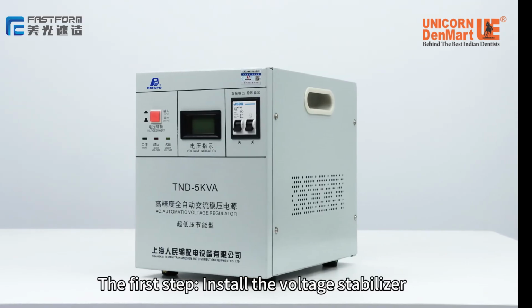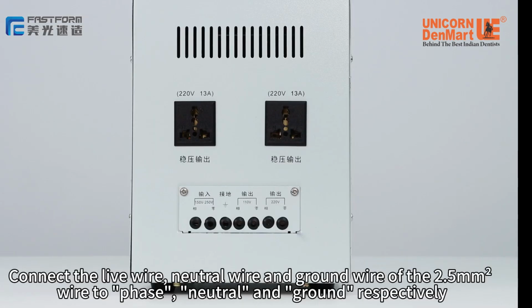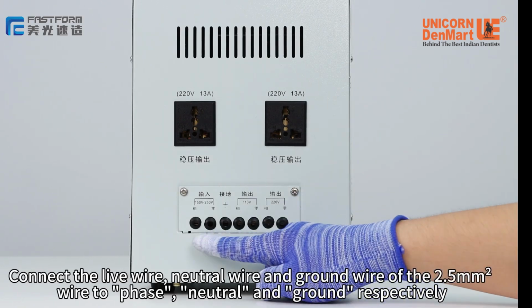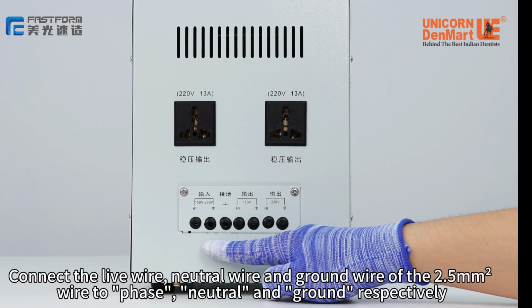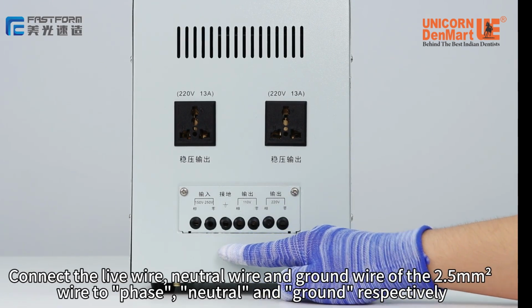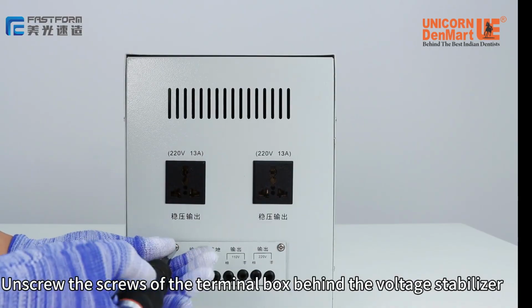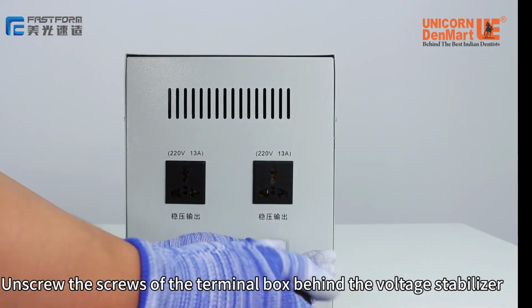The first step is to install the voltage stabilizer. Connect the live wire, neutral wire, and ground wire of 2.5 square millimeters to the phase, neutral, and ground respectively. Unscrew the screws of the terminal box behind the voltage stabilizer.